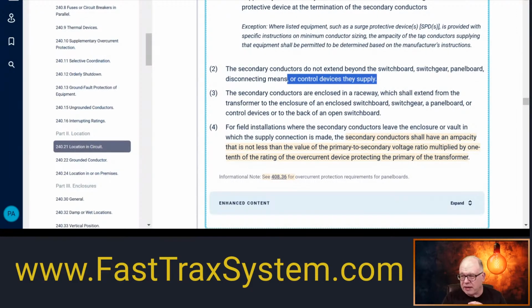Okay, so whether I'm hitting a disconnecting means there and doing what we said earlier, or we're actually coming out of the secondary and we're going into a panel board, which is going to have a main breaker mounted on it inside of an enclosure, right? The panel board's the guts. So in that scenario, it can't extend beyond it. So what we were saying is, once those come out of the secondary, and Dan was pointing to this, once they connect into the actual disconnecting means, whatever we're doing, or the breaker in a panel board, let's say, once that takes place, then that's it. You've met that rule, right? They're not tapped onto. Again, you can't tap a secondary and come out and try to hit something else. Look, it comes straight out of the transformer right into that enclosure.